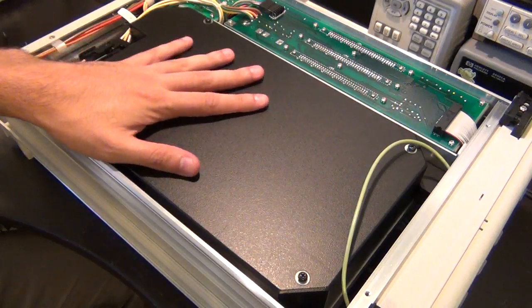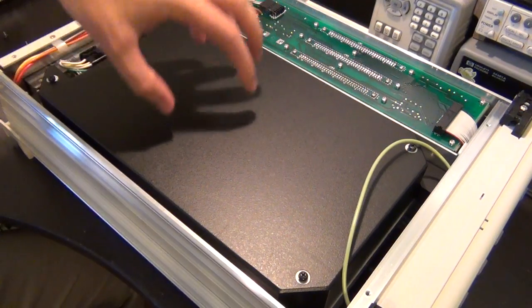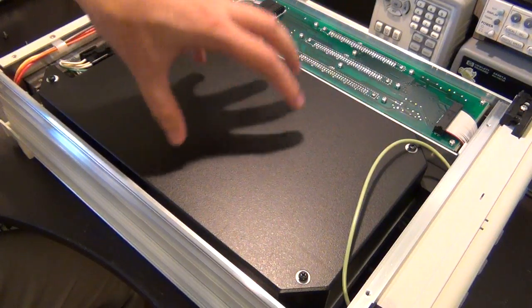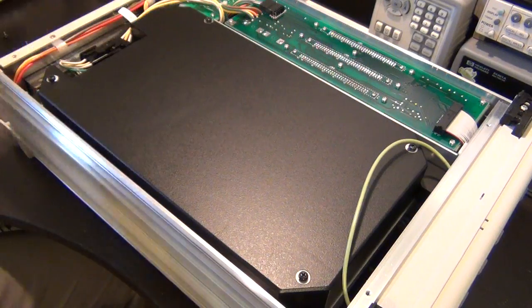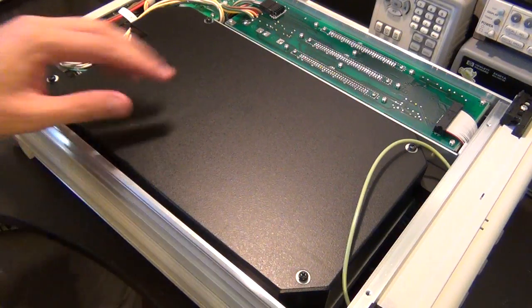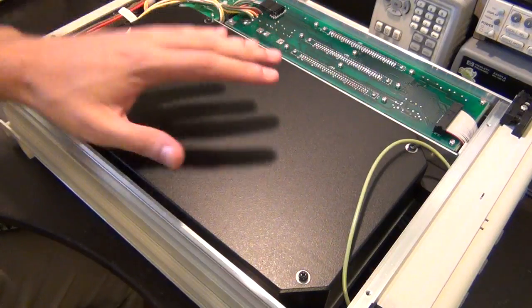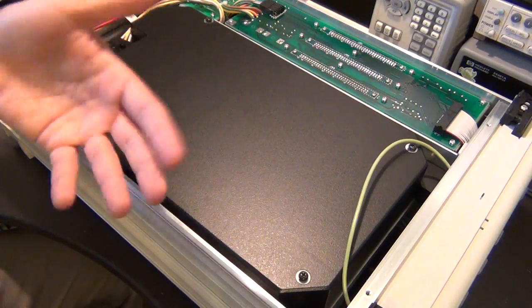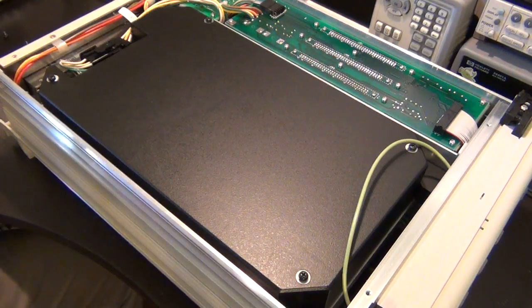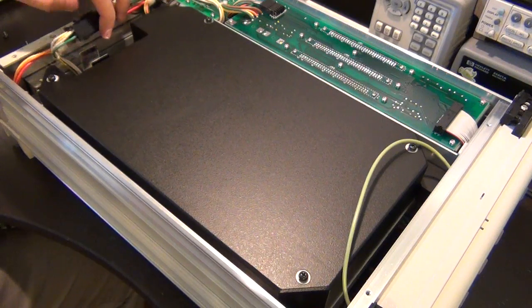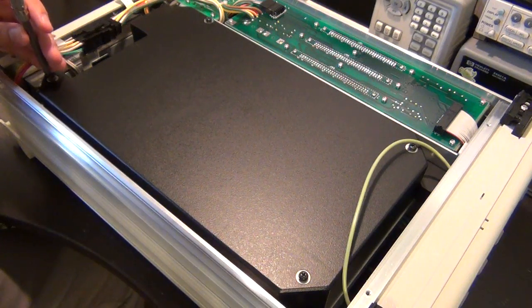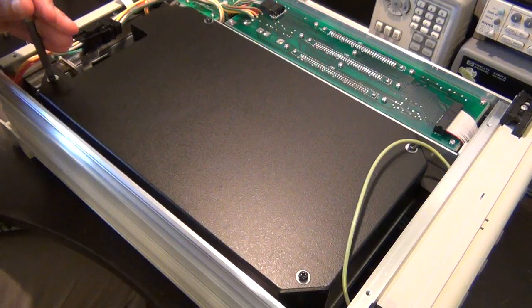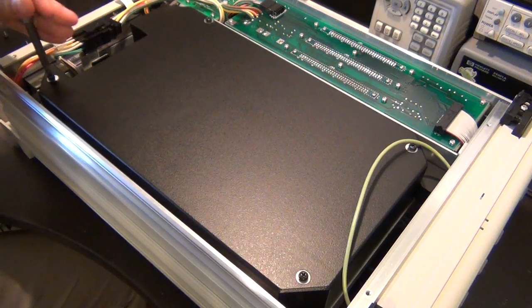Okay, so here's the back of the unit. I just flipped the whole thing upside down. Again, you can see there is another chamber, a cage here that is painted black. And remember, this thing is painted with a non-reflective paint both on the inside and on the outside, so that the light doesn't bounce around and any stray light is caught and does not reflect back onto the sensors to throw off the measurements. Similarly, this thing has 4 screws.